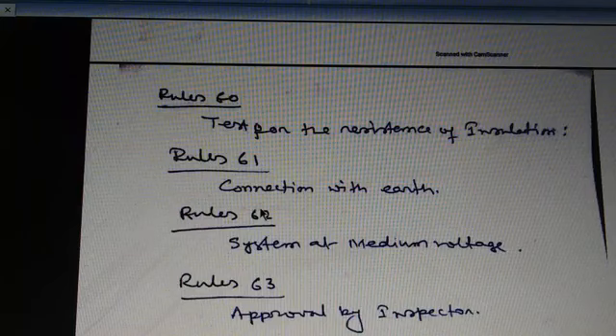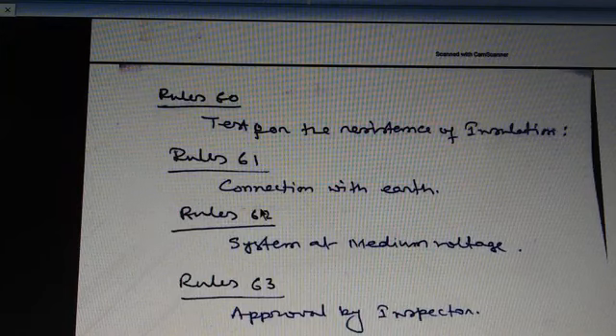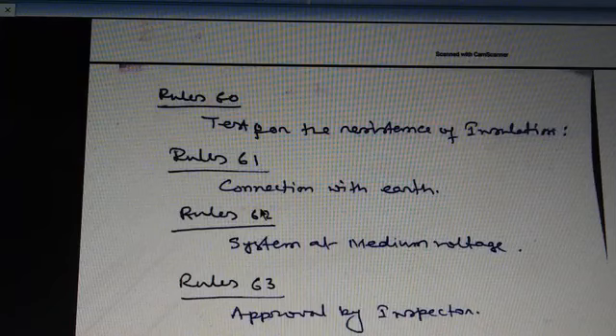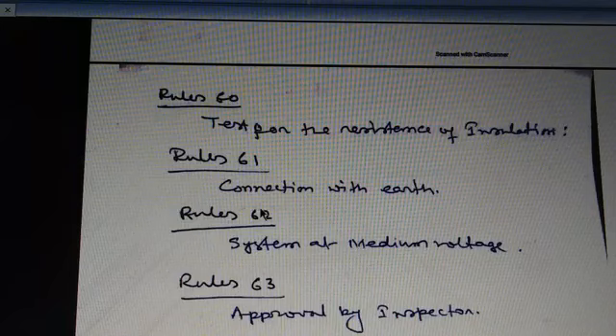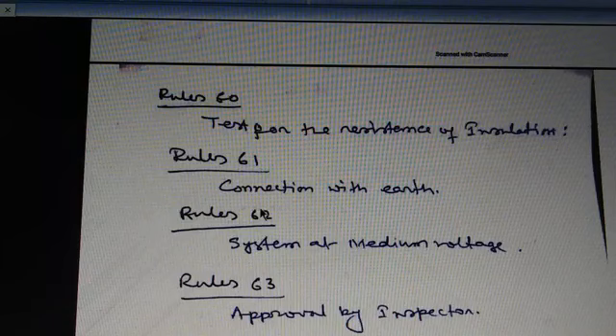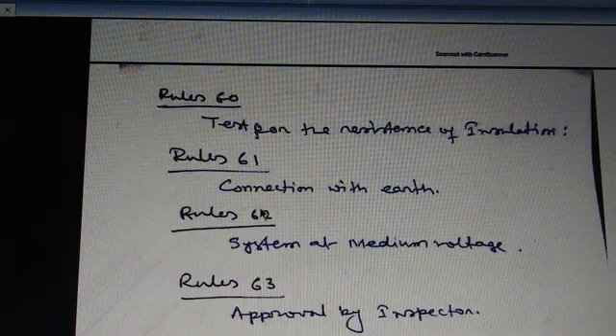Next point, in the case of a system comprising electric supply lines having concentric cables, the external conductor of such cables shall be earthed by 2 separate and distinct connections with earth. Next point, the connections with the earth may include a link by means of which the connections may be temporarily interrupted for the purpose of testing or for locating a fault.